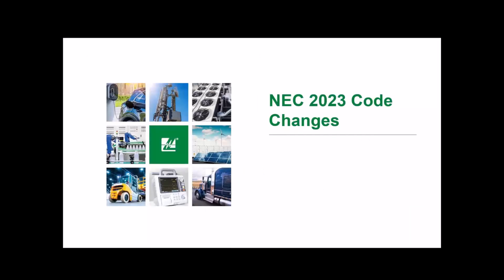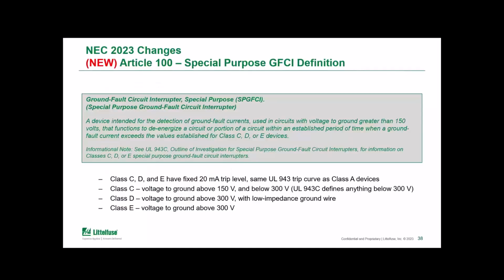So now that we've really covered what special purpose GFCI is all about and how it's different than some of the traditional GFCI protection, we probably can take just a quick look at a couple code changes that have already happened that incorporate this technology. In the 2023 edition of the NEC, one of the major changes that anyone will first see if you've looked at it is all the definitions being centralized in Article 100. So in Article 100, there was a new definition added for a special purpose ground fault circuit interrupter.